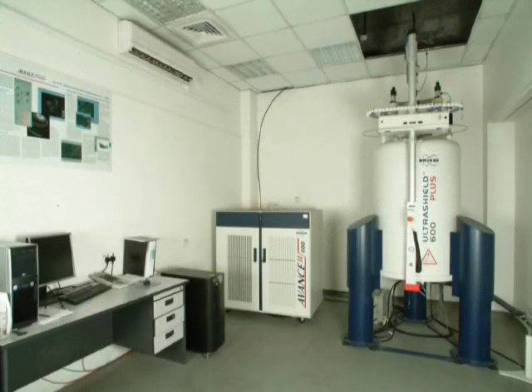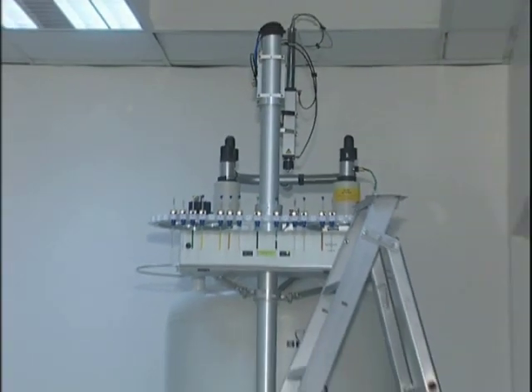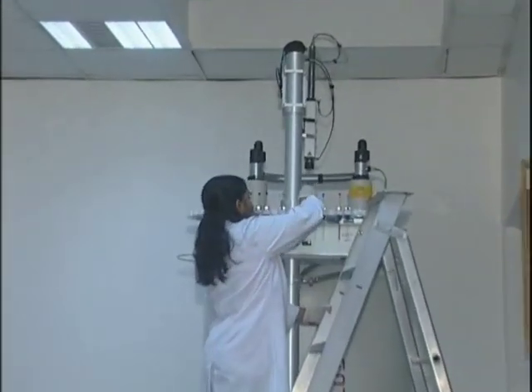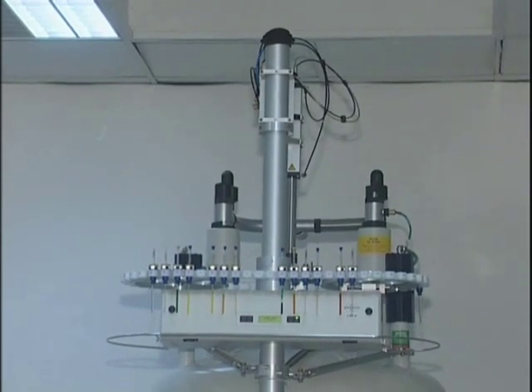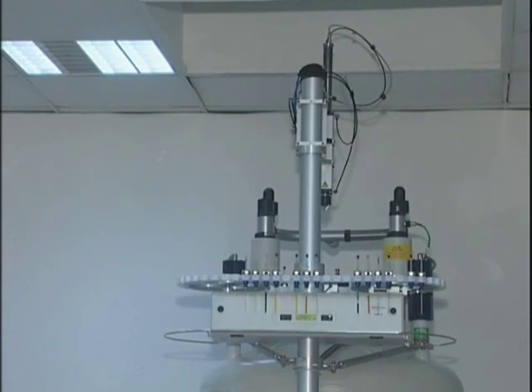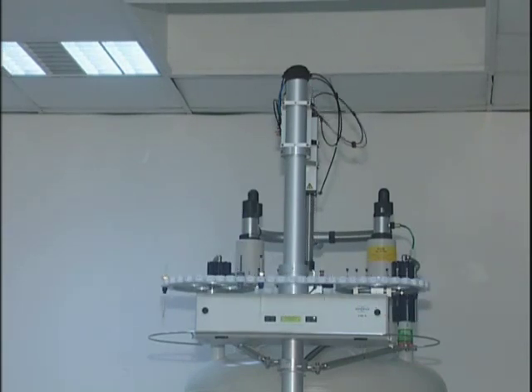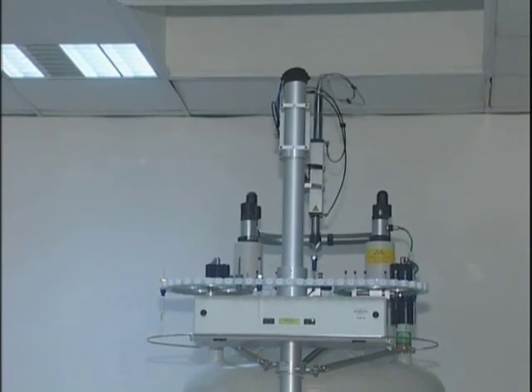The high-resolution 600 MHz NMR from Bruker, Switzerland, is perhaps the most prestigious instrument available in the university today and perhaps in the region. The spectrometer features ultra-shielded technology with minimal stray field. It is a three-channel spectrometer allowing triple resonance experiments often needed for protein, peptide, and other natural product and biological studies. The highly stable and homogeneous magnetic field provides excellent line shape and sensitivity.